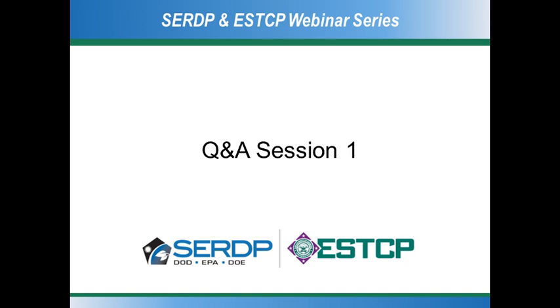Thank you so much. And one last question before we transition to the second part of your talk. Can you tell us what you are using to model the components of both systems? So to go back and answer your question, the software we're using underground is TRNSYS. You can also use TRNSYS above ground, but part of the problem with that is, it's not a problem, I'm sorry. You can use eQuest, a program like eQuest, Trane Trace, Carrier HAP. You model the inside of the building, you get the coil loads, and then once you've gotten the coil loads done, you take those coil loads and put them into TRNSYS and you model the underground loads.